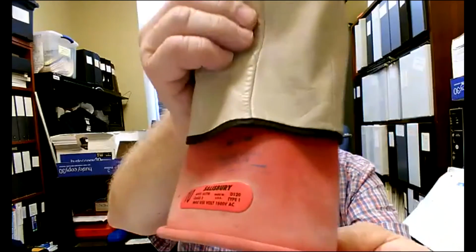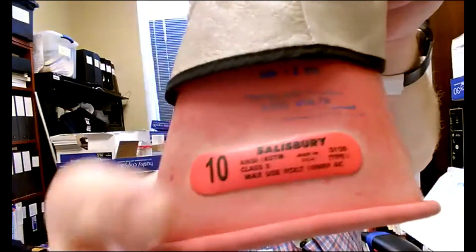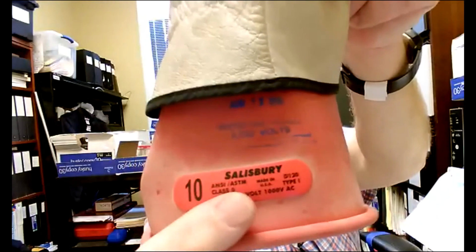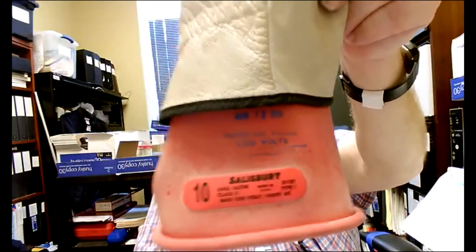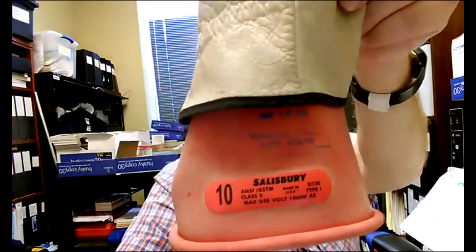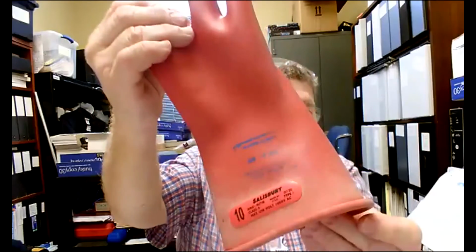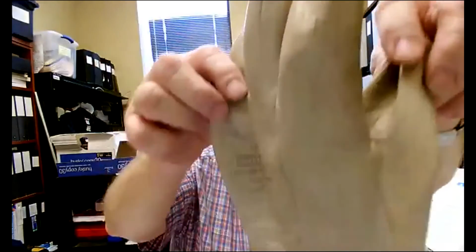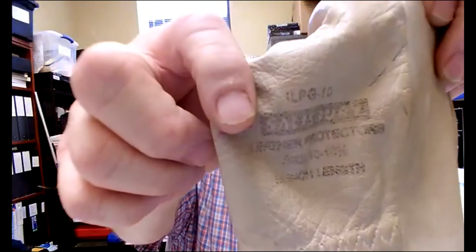If you notice here, when I go up here, you can read that the rating on it is 1,000 volts AC, and it's been tested at 5,000 volts. That testing happens. I send these out periodically to a lab in Goldsboro, to Sharp Safety, and they test the rubber part. This is the actual part that protects you electrically. It's a voltage rated rubber. And then you put the leather protector on top of that. Not just any leather protector, but one that's actually listed by Salisbury, that same company, that's approved for it.